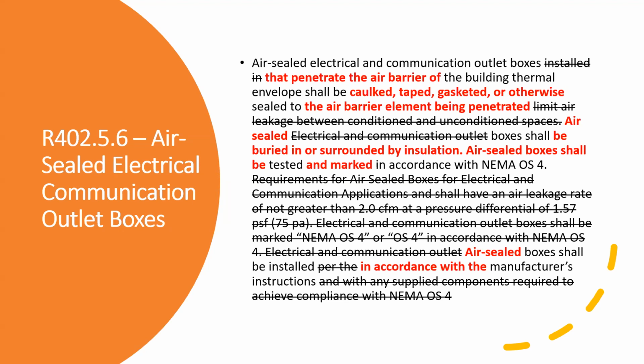We've talked about it in previous webinars: confusion about electrical boxes needing to meet the NEMA OS4 standard. Really, the intent in the beginning was if you're going to use a manufactured air-sealed box, it needs to be tested for air tightness. Just like can lights have to be ICAT rated, insulation contact airtight, they have to be tested and stamped or stickered to say they've been tested for air tightness.